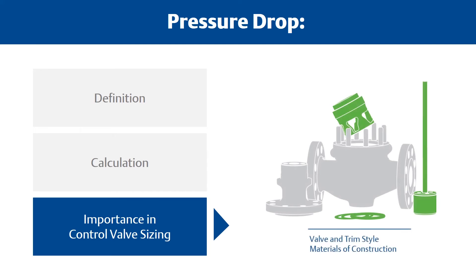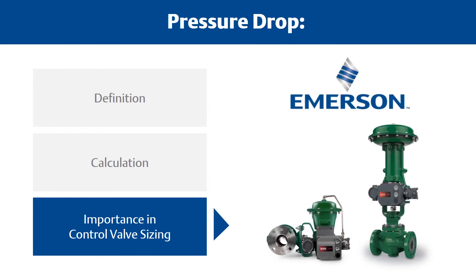Control valve flow is a function of both the pressure drop across the valve and the valve travel. In control valve selection, pressure drop plays a role in determining not only the valve and trim style, but the materials of construction as well. Higher pressure drops generally require highly engineered control valves for good performance. Control valve manufacturers publish charts with maximum pressure drop limits for their control valves. The charts for Emerson's Fisher control valves can be found in their product bulletins.